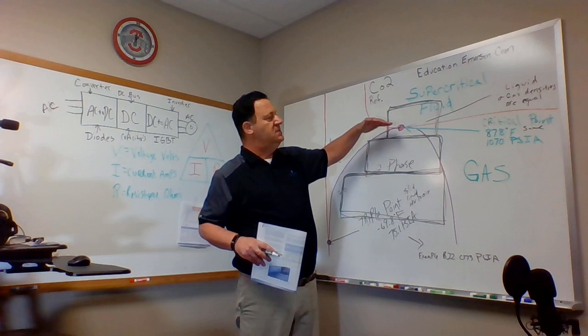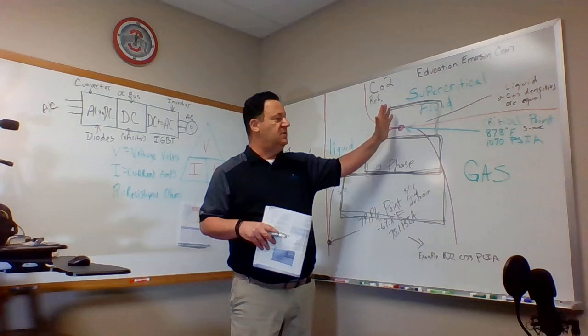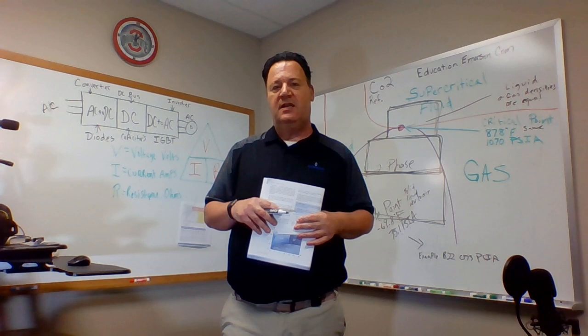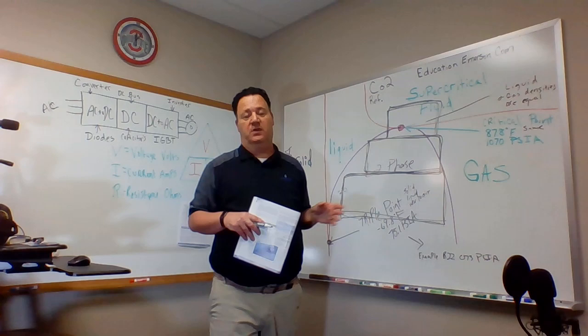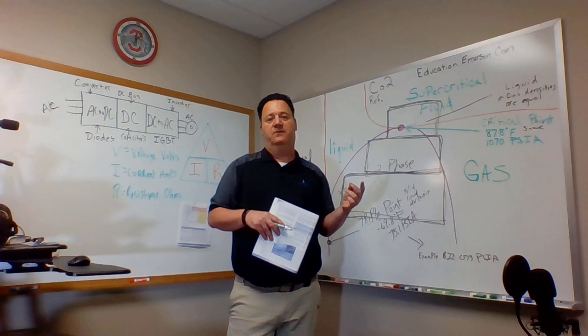In certain areas of the world, let's say Canada, for example, we would primarily be in subcritical all the time, but they purposely, where you need sanitization, whether you're working with fish or anything to do with sanitary, cleaning up, if you're working with food, meats, anything like that, where you use a high volume of hot water, they purposely push that in transcritical. They manipulate the pressures to utilize that heat from the transcritical, okay? They reclaim that, and they use it for water, they use it for heat, they use it for dehumidification. So there's a good side to that.